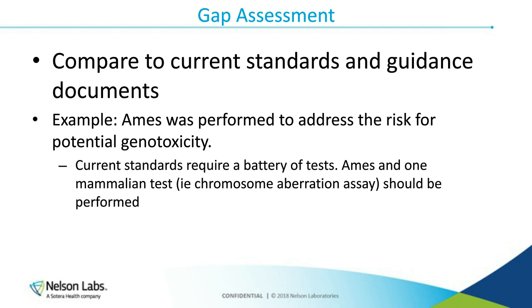So in this case, I would recommend they complete their genotoxicity battery by performing one of the mammalian tests, or look and see if they've done some chemical testing and relate those results through a toxicological risk assessment to address genotoxicity. Once we identify the gap, we will recommend the testing, but that recommendation depends specifically on the unique situation of the manufacturer, where we want to try to use the information they already have available. We're always keeping in mind that we are assessing this based on risk. We don't want to just say, go and do a test so you can check off the box. Make good decisions about the way we're addressing these gaps.